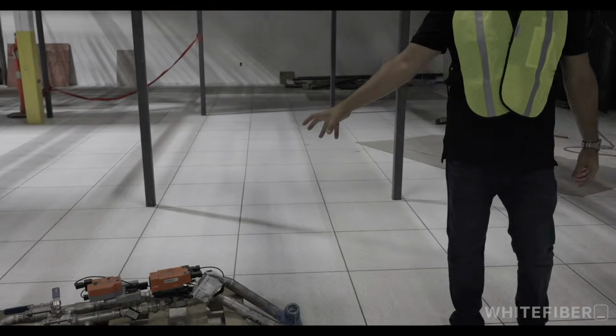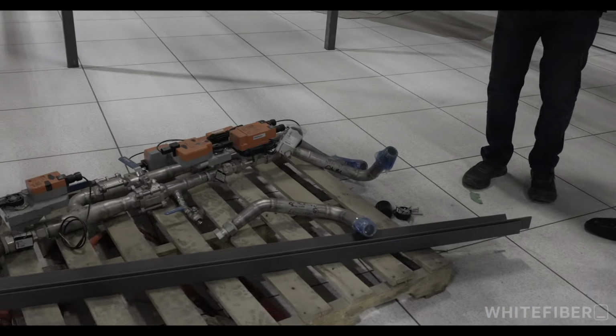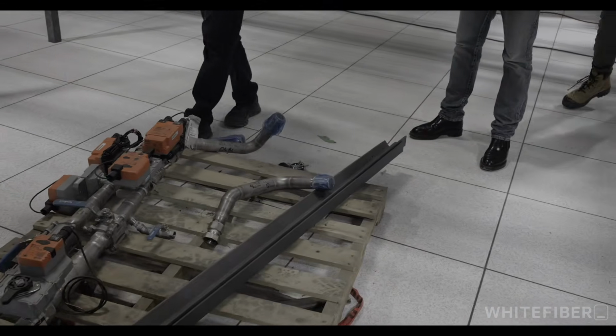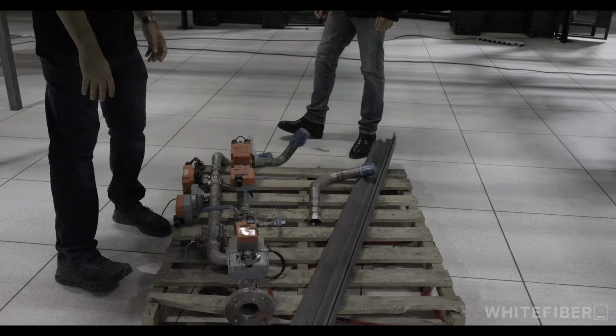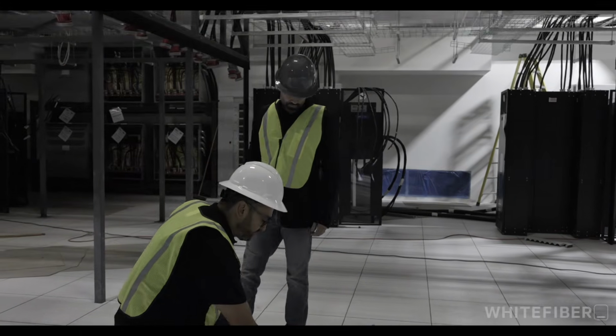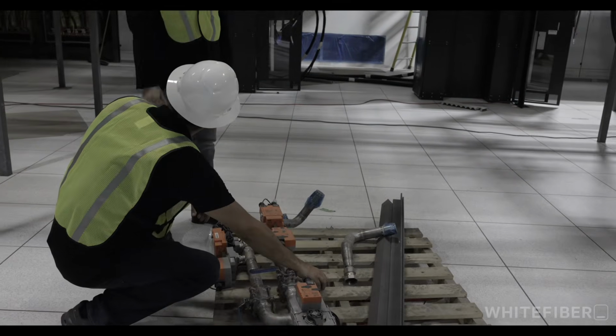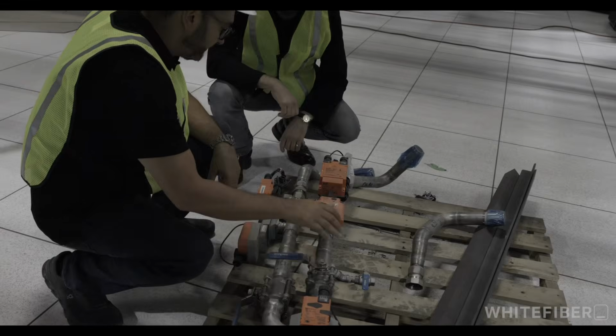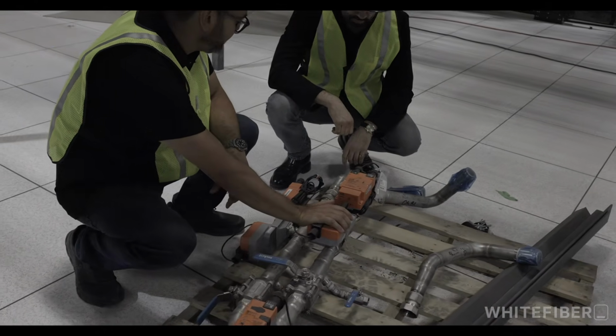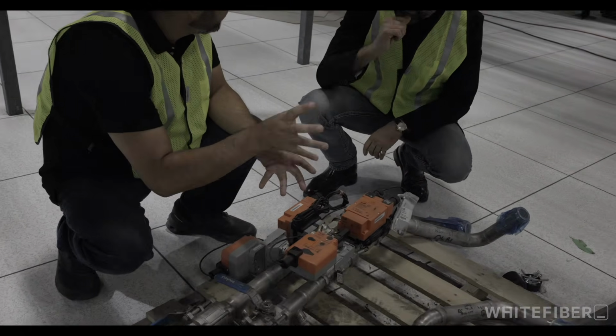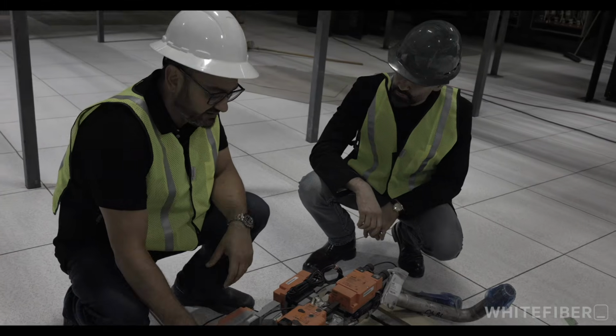So over here we have a piece of the manifold that's underneath the raised floor. So basically each cabinet, each direct-to-chip liquid-cooled cabinet connects to one of these valves, and this is how they get their cooling. These are automatic shut-off valves. If anything were to happen, we can isolate and shut off one cabinet of the installation.